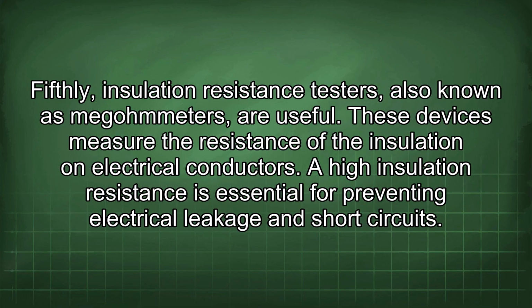Fifthly, insulation resistance testers, also known as megohmmeters, are useful. These devices measure the resistance of the insulation on electrical conductors. A high insulation resistance is essential for preventing electrical leakage and short circuits.